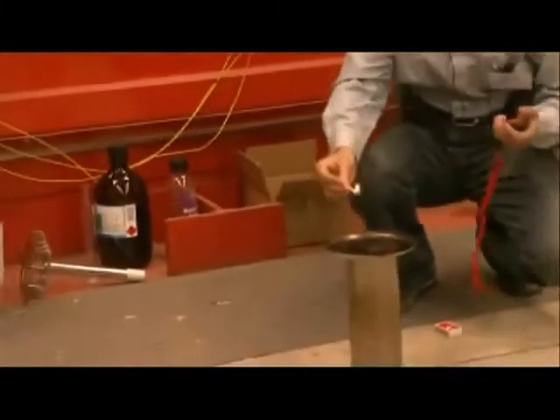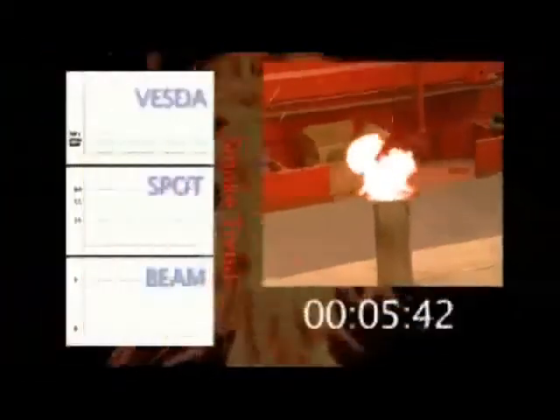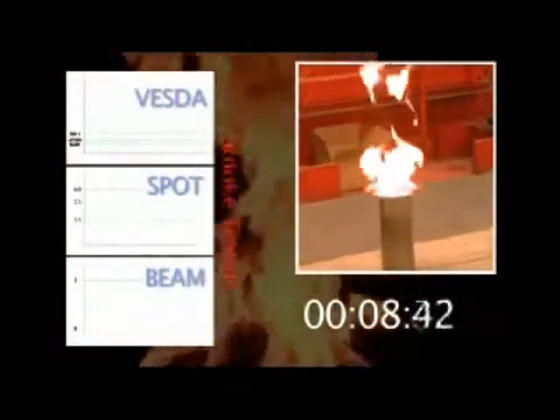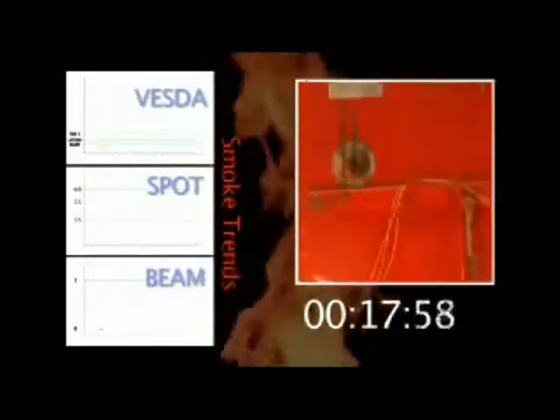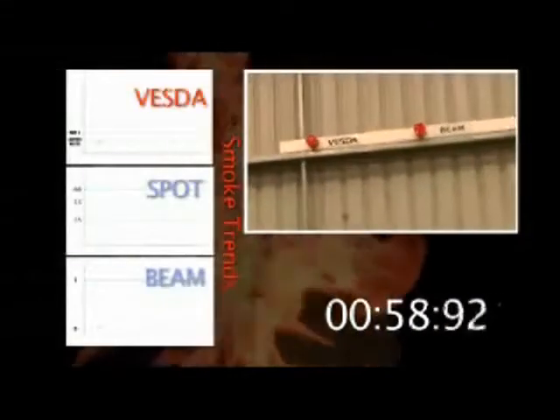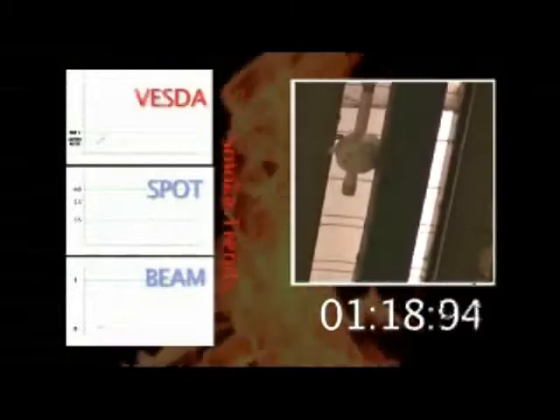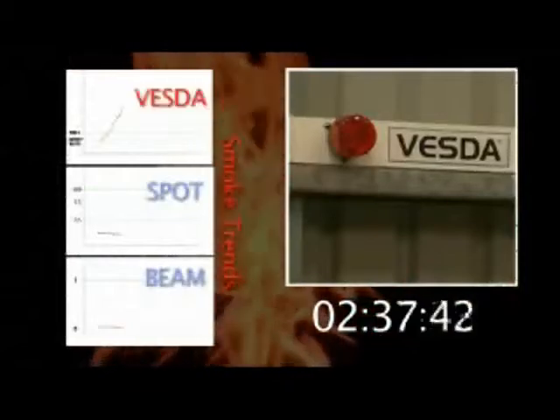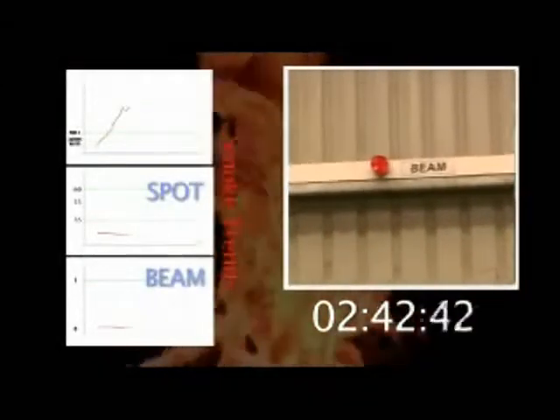Heptane. The second test is conducted to UL and EN standards and features one hundred millilitres of heptane to produce a fire of around ten to twenty kilowatts, which is much larger than the timber fire, yet still controllable. The burning heptane creates a large flame with black smoke. In less than sixty seconds, the VESDA has already registered the presence of smoke and triggers the first alert after one minute eighteen seconds. At two minutes thirty-five seconds, the VESDA has triggered fire one alarm, while there is still no indication of smoke from the point or beam detectors.